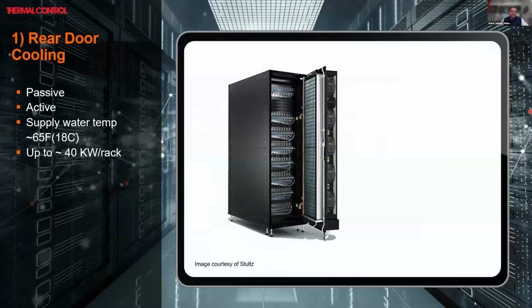If you're from a data center background, you already know this. But if you don't, this is how the rear door heat exchanger looks like, and there are servers in here, and there is a supply water temperature of 18 degrees centigrade. This has a capacity of up to 40 kilowatt per rack. And then there is chilled water or dielectric, let's call it chilled media, which is being transferred from the central distribution unit to the rear door heat exchanger.